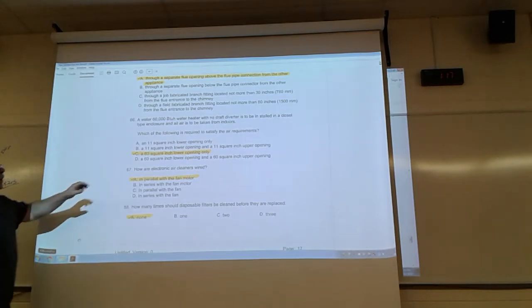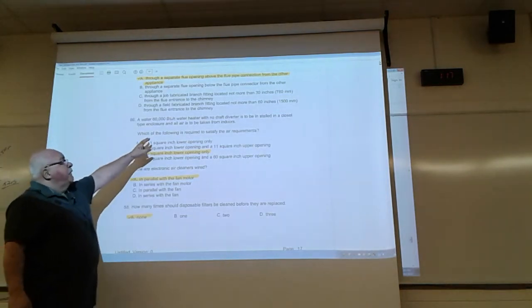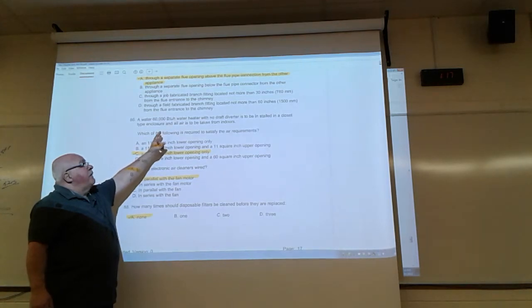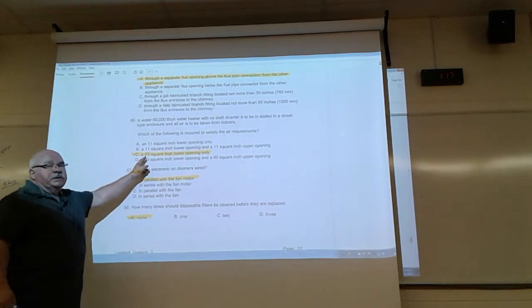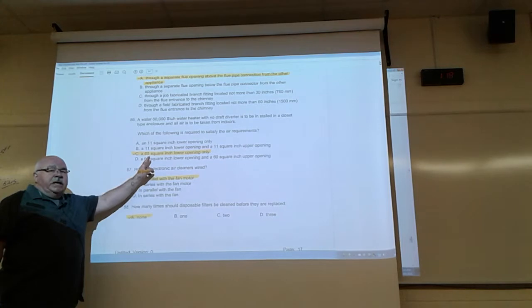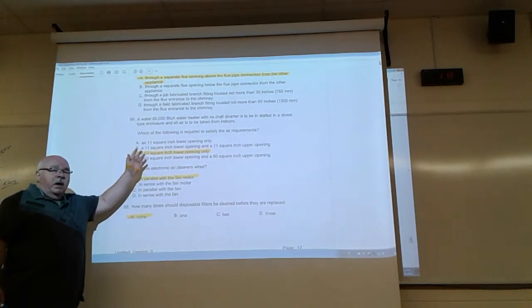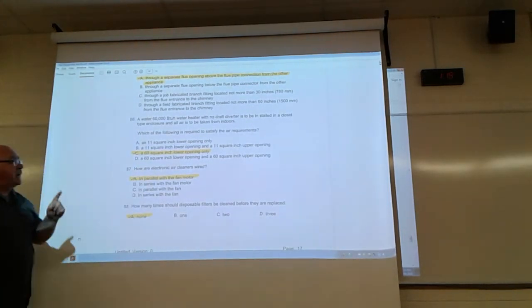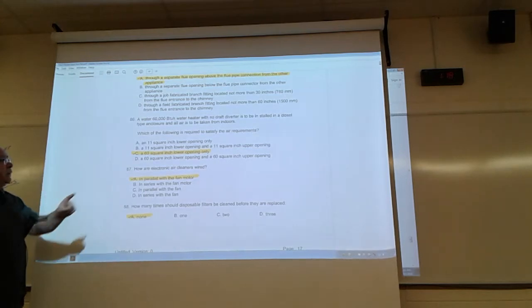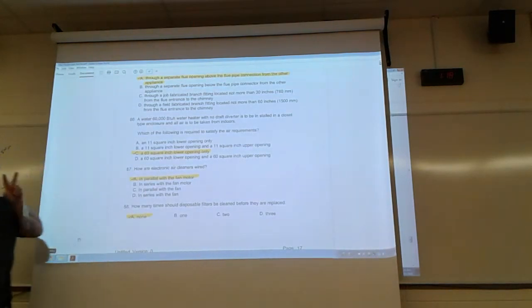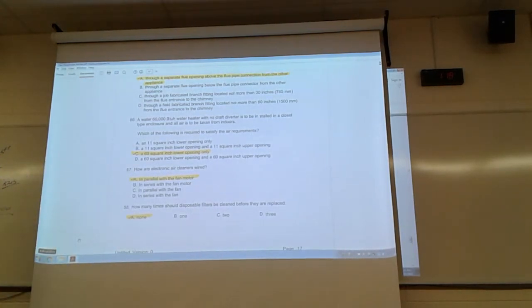Now, it does say in the code that if the appliances do not have draft control devices, you only need a combustion air opening 6 to 18 inches off the floor. But if you have multiple appliances and one of those appliances has a draft diverter or draft hood, then you need 2 openings of the same size, one at the bottom for combustion, one at the top for ventilation. This doesn't count. Okay, 87, how are electronic air cleaners wired? In parallel with the fan motor.